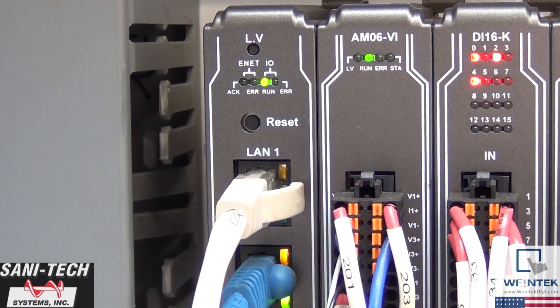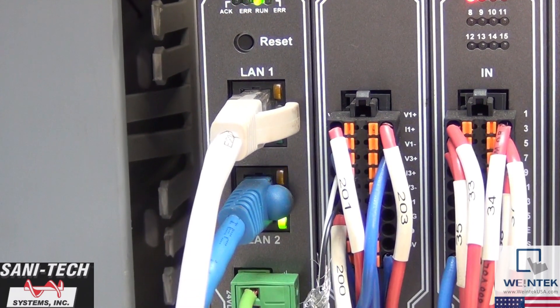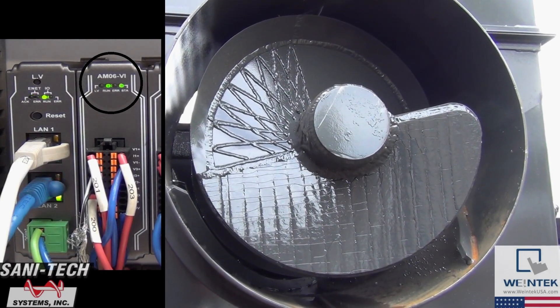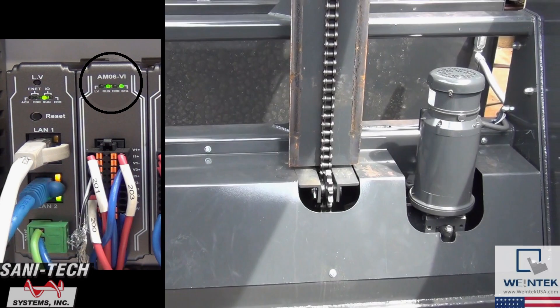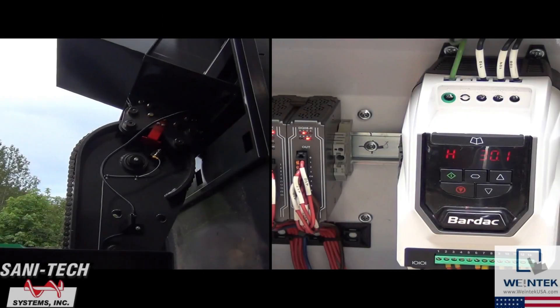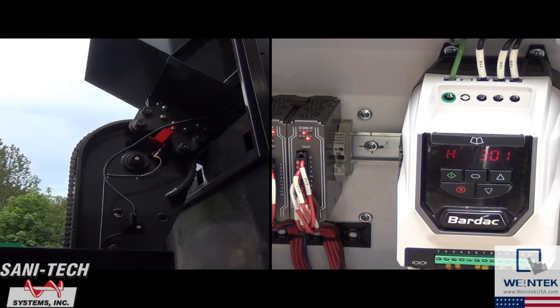Our IRETN is our Ethernet Coupler, which enables communication between CODESYS and our IO modules. The IRAM06 is our Analog IOs module, which is used to retrieve current data from both the auger and dumper. This data is then used within our CODESYS program to perform certain calculations.